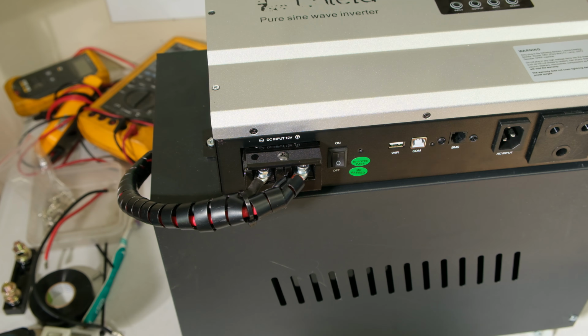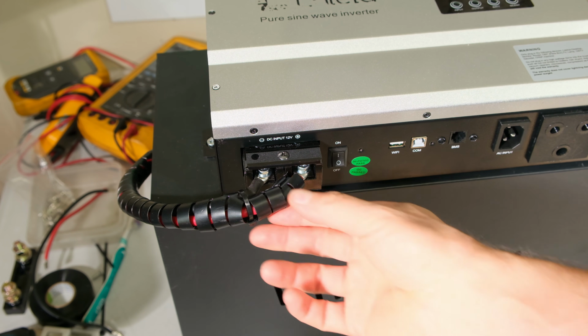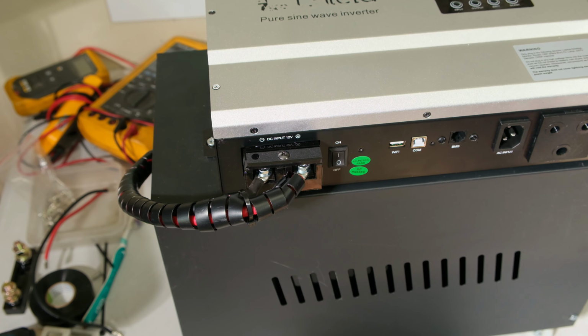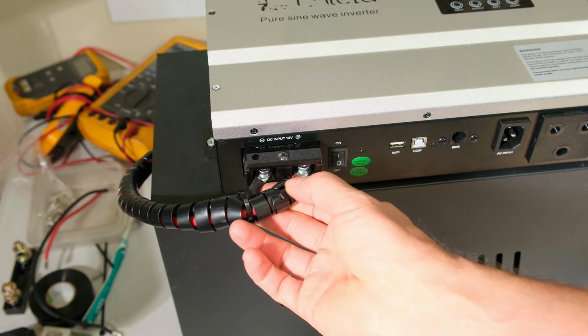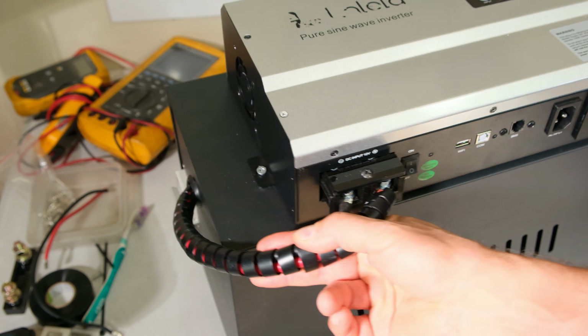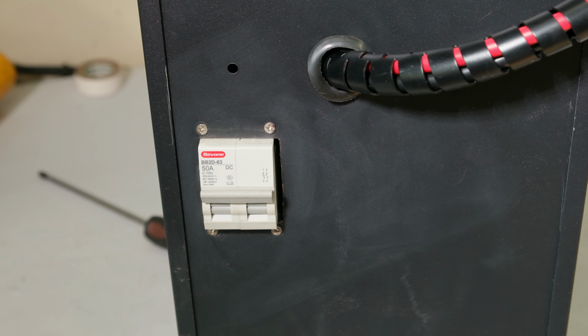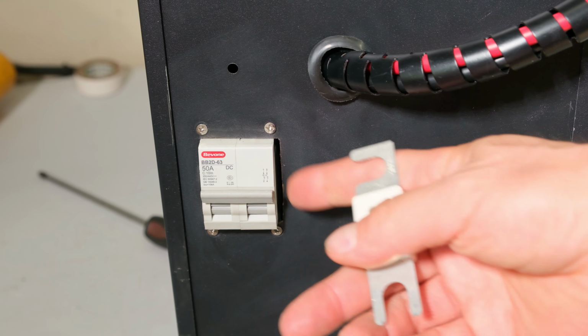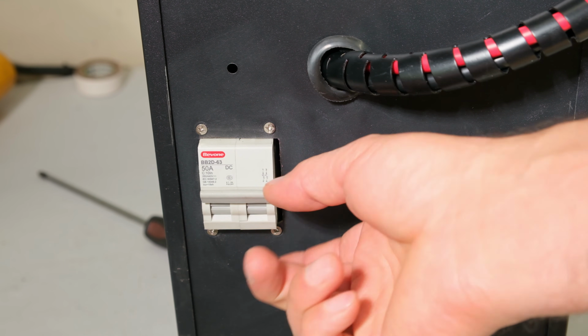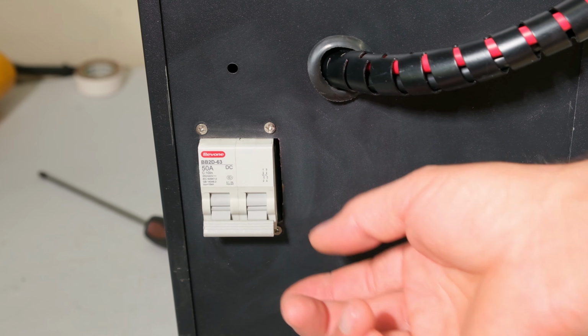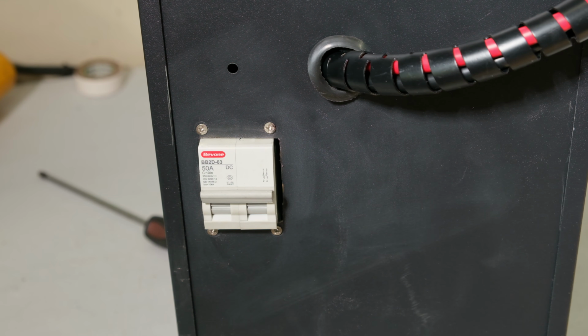Lastly, the unit does need thicker wires, so I've changed the wires from the ones supplied to these 16mm copper wires. Any device connected directly to a battery, specifically a lithium battery, needs to have either a fuse or a circuit breaker, and there I've installed a 50 amp DC circuit breaker to protect that battery under short circuit conditions.